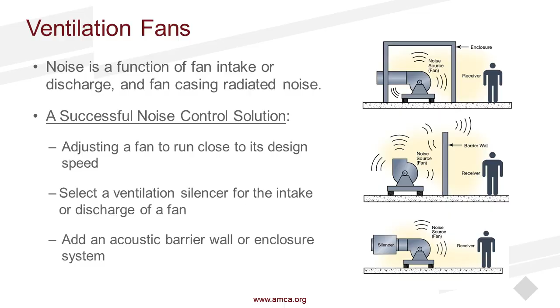If you look here in the upper left-hand corner, this is actually a fan at the AMCA laboratory. And what I like is we don't get good pictures of silencers on fans. And what's really nice here is it's a nice round intake silencer with an internal sound-absorbing bullet and a perforated inner shell and insulation thickness. So you're getting the best of the best here based on balance of pressure drop on the intake and acoustics versus a function of length and diameter. And then also here you have a rectangular discharge upblast.